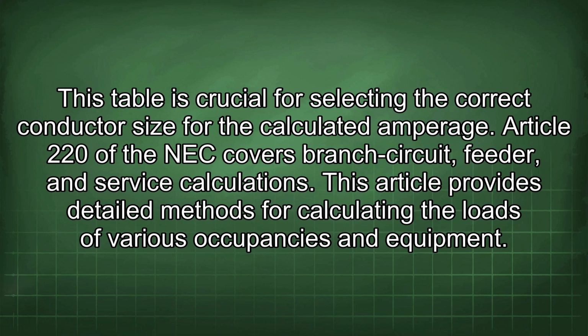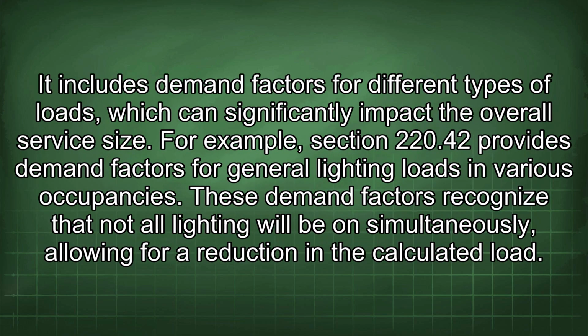Article 220 of the NEC covers branch circuit, feeder, and service calculations. This article provides detailed methods for calculating the loads of various occupancies and equipment. It includes demand factors for different types of loads, which can significantly impact the overall service size. For example, Section 220.42 provides demand factors for general lighting loads in various occupancies. These demand factors recognize that not all lighting will be on simultaneously, allowing for a reduction in the calculated load.